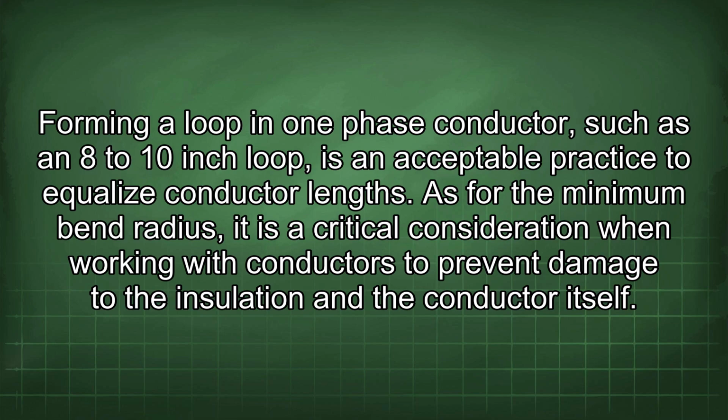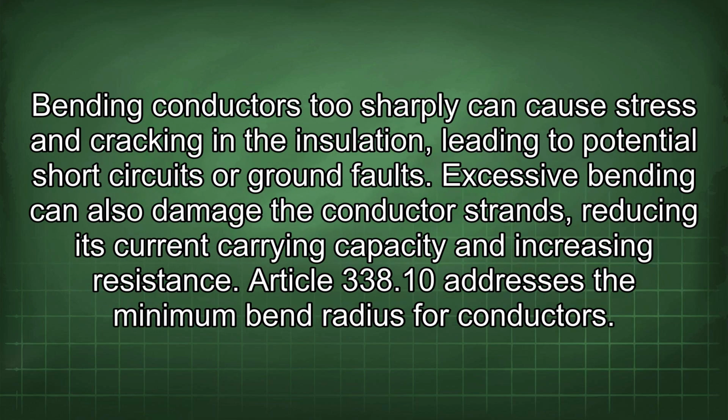As for the minimum bend radius, it is a critical consideration when working with conductors to prevent damage to the insulation and the conductor itself. Bending conductors too sharply can cause stress and cracking in the insulation, leading to potential short circuits or ground faults. Excessive bending can also damage the conductor strands, reducing its current carrying capacity and increasing resistance. Article 338.10 addresses the minimum bend radius for conductors.